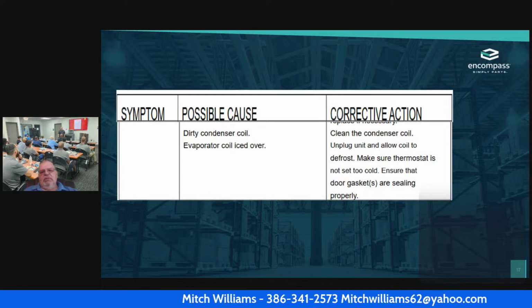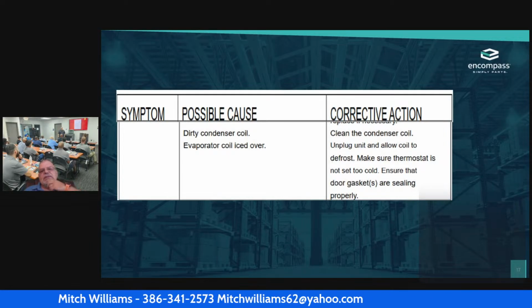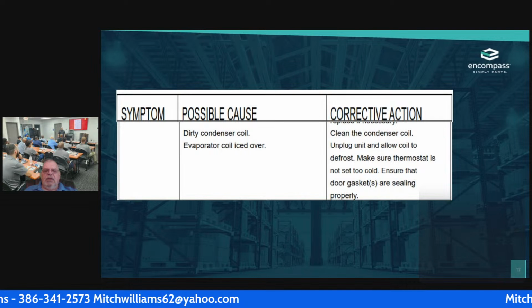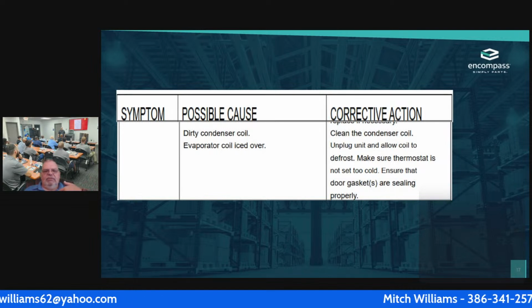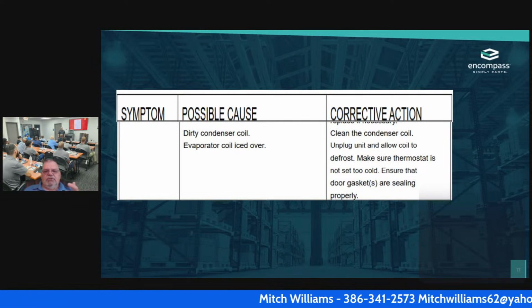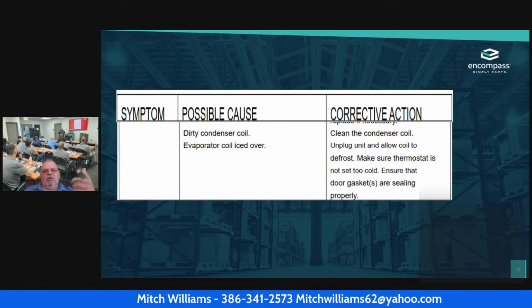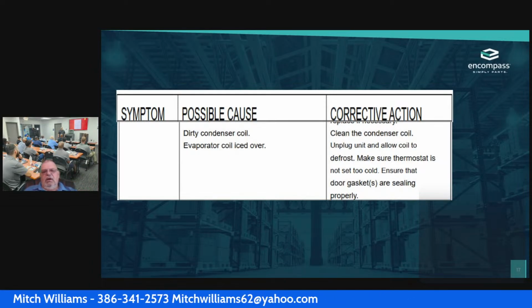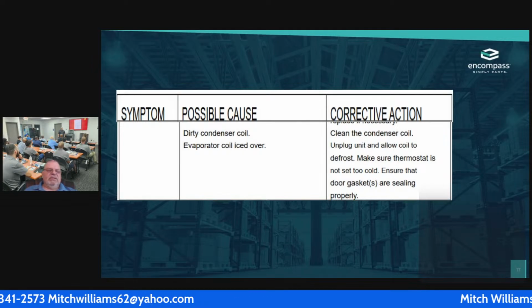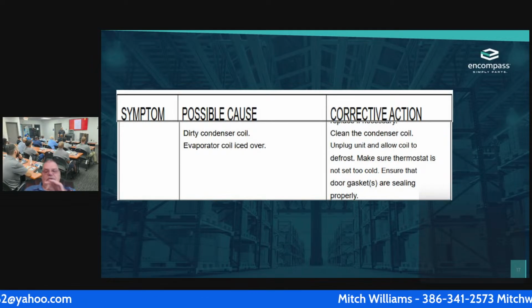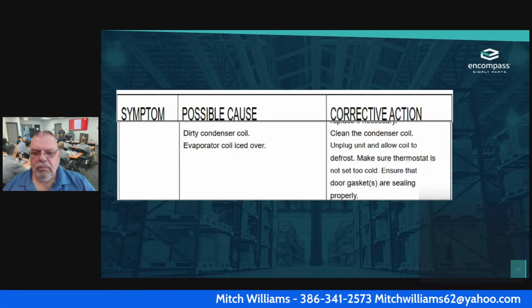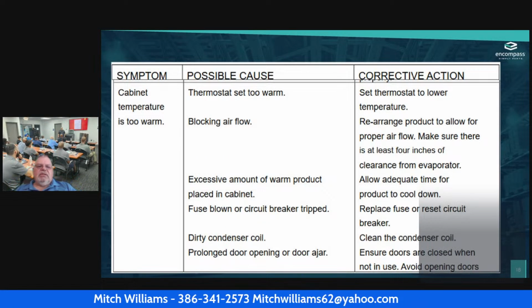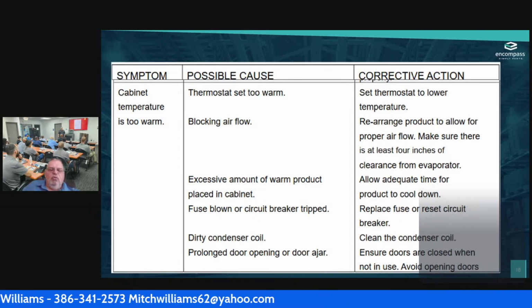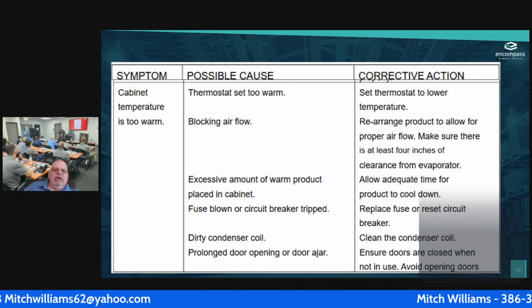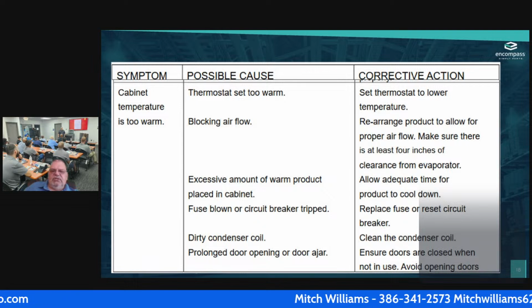Then I can use my steamer to steam all the coils clean. Of course, you have to have the unit unplugged. And then make sure that the thermostat is not set too cold. That causes this. So ensure that the door gaskets are sealing properly. That's one of the other things. Okay. So if something happens in the cabinet and the temperature is too warm, how am I going to do this? I'm going to check the thermostat, make sure that it's not set too warm. If it is, I'm going to turn it down.